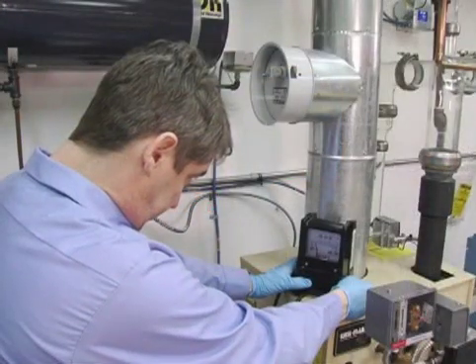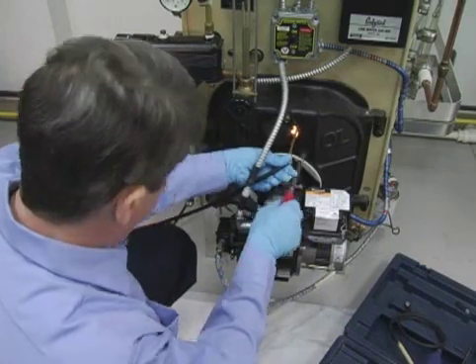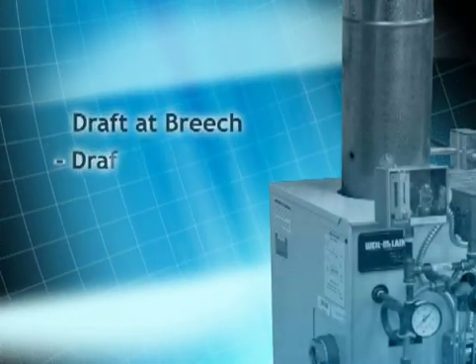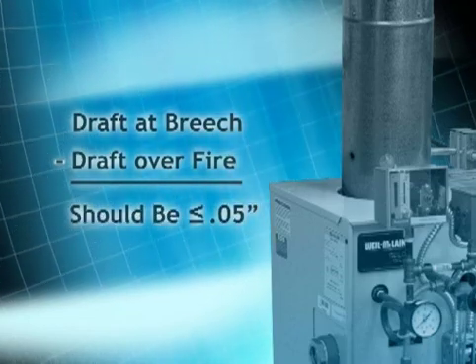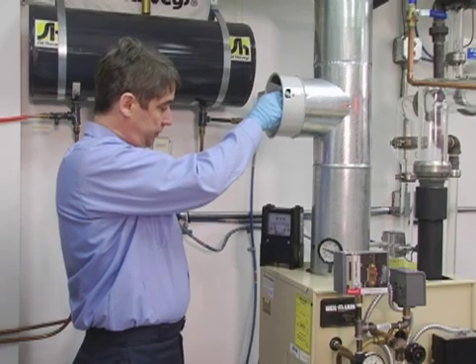To begin the draft test, you must zero out the draft gauge. Then check for sufficient draft at the breech and for the manufacturer's recommended draft over the fire — typically negative 0.01 to negative 0.02 inches of water column for residential units that operate with negative draft. A differential of more than 0.05 inches between the two readings indicates heavy sooting or air leaks in the appliance. If the draft is not in line with the manufacturer's recommendations, adjust the draft regulator until the proper draft is achieved.